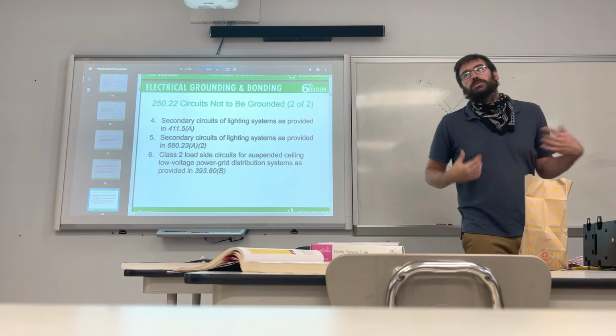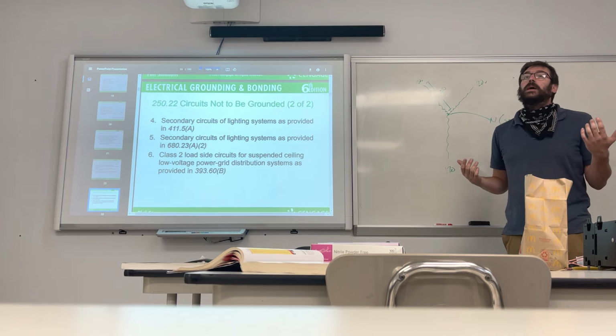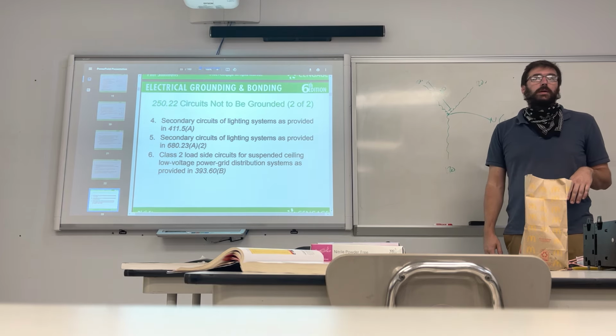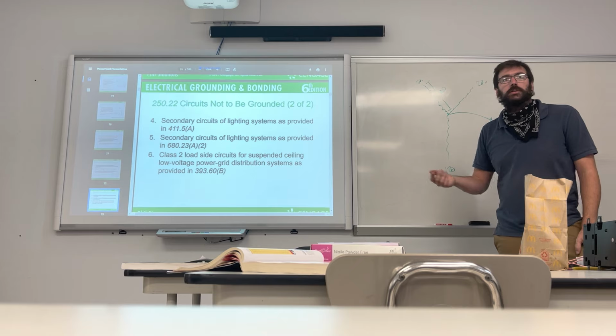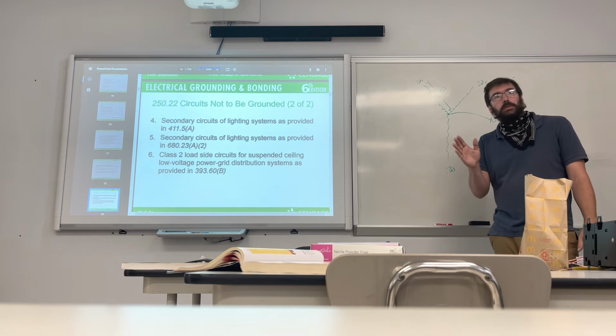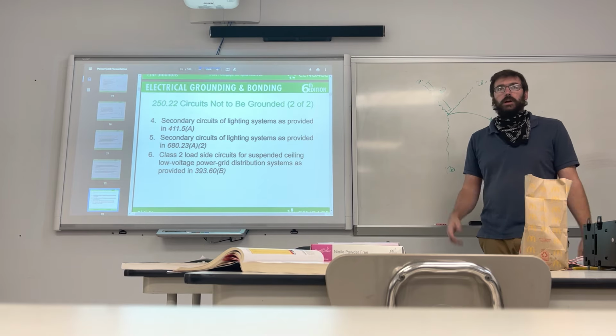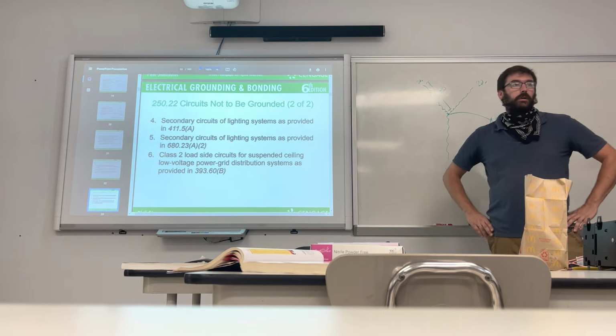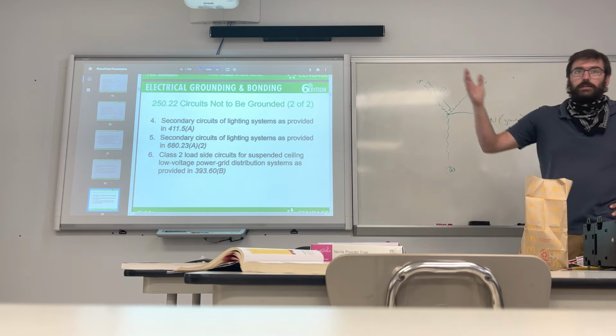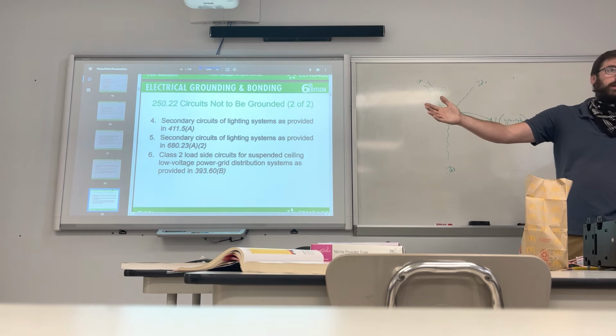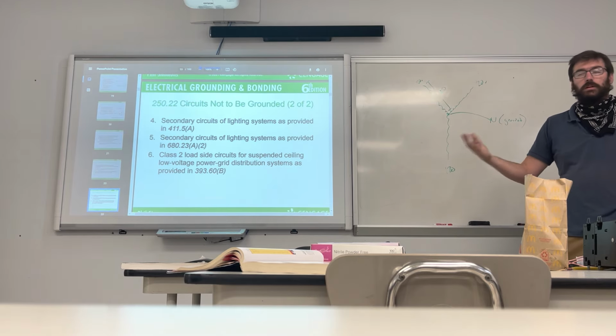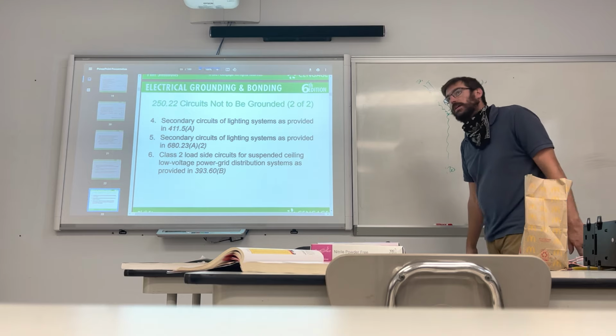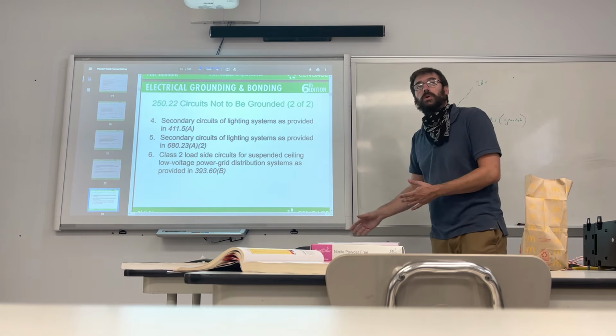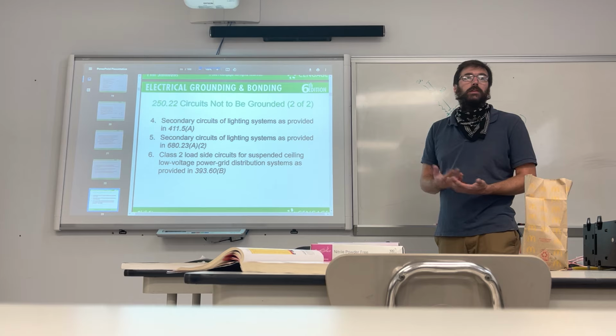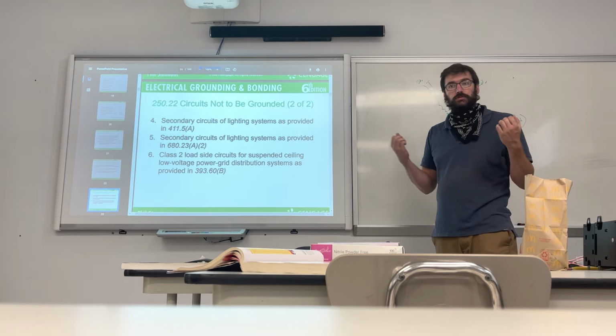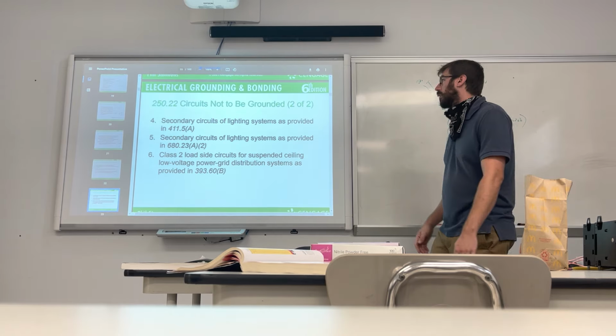But once again, that's us being electricians. We do a lot of things that might not even be in the code book. Like you put up a service on a house and there's windows everywhere, and you can't be within 3 feet of a window. You don't tell the inspector, oh, I just thought. If you go with a calculated reason as to why you did it, that's your variance. So always have a reason why. Even if it's not to code and you did something a little weird, always have a firm reason why. And usually if that reason is founded in science, you'll usually be let go.